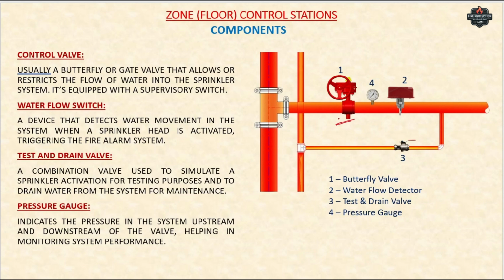Under normal conditions, the zone control valve remains open, allowing water to flow freely through the system and ensuring that all sprinkler heads within that zone are ready to activate in case of fire. So this valve is basically open all the time, do not close this valve. If closed, it will send a signal to the fire alarm panel.